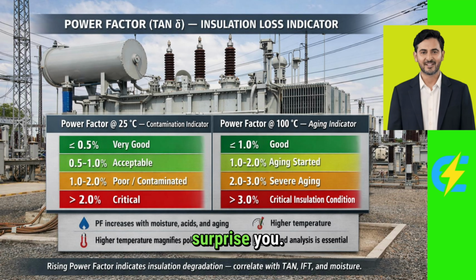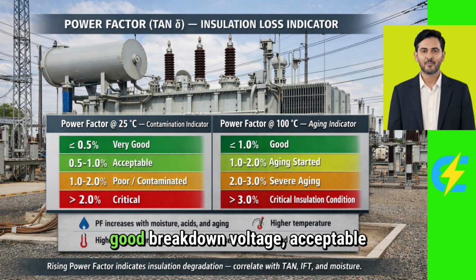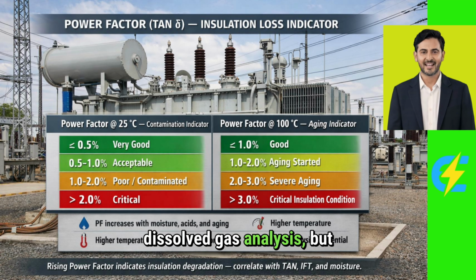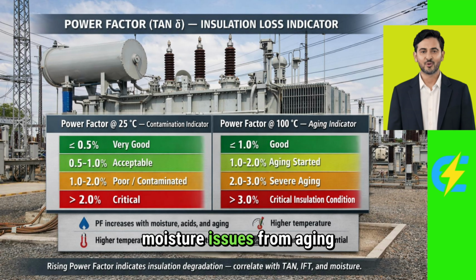Here's something that might surprise you. Many transformers fail with good breakdown voltage, acceptable dissolved gas analysis, but with high power factor. This happens because power factor reveals what is chemically wrong, not what is temporarily stable. It's like checking if someone can lift a heavy weight today versus checking if their muscles are slowly wasting away. Power factor is a truth-revealing test. It shows dielectric losses that other tests might miss. Temperature helps us separate moisture issues from aging issues. And high power factor at 100 degrees means oil life is ending, even if other parameters look acceptable.